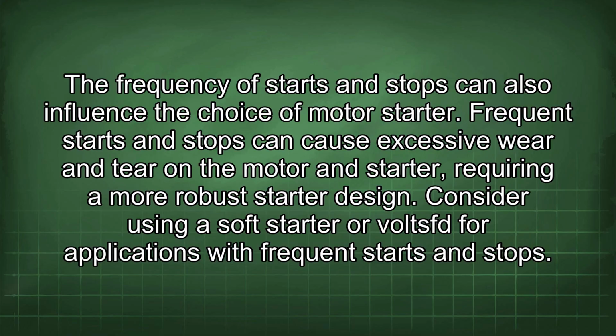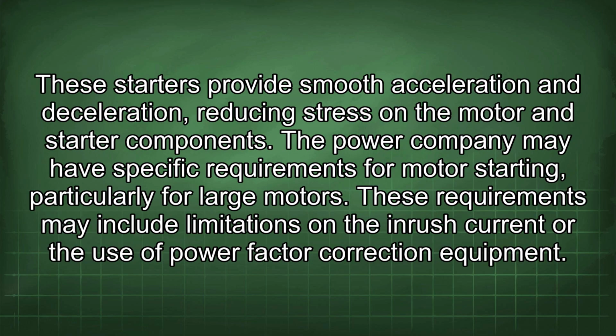Frequent starts and stops can cause excessive wear and tear on the motor and starter, requiring a more robust starter design. Consider using a soft starter or VFD for applications with frequent starts and stops. These starters provide smooth acceleration and deceleration, reducing stress in the motor and starter components.